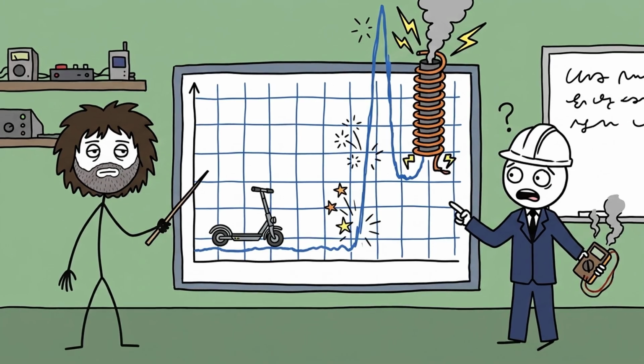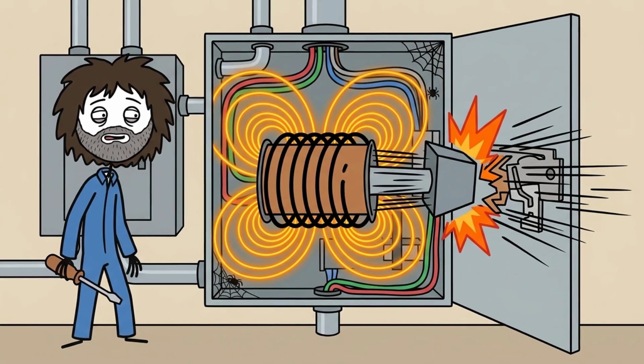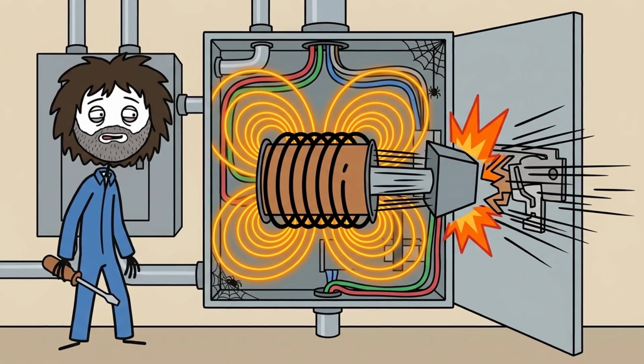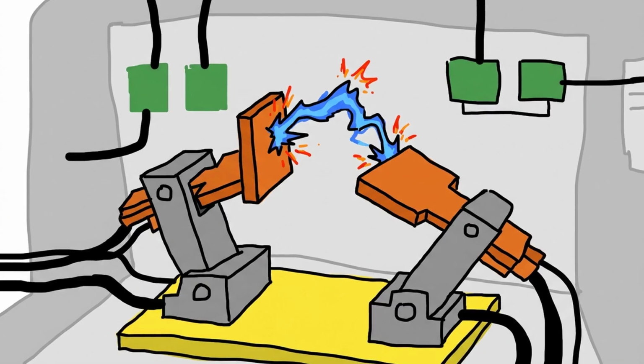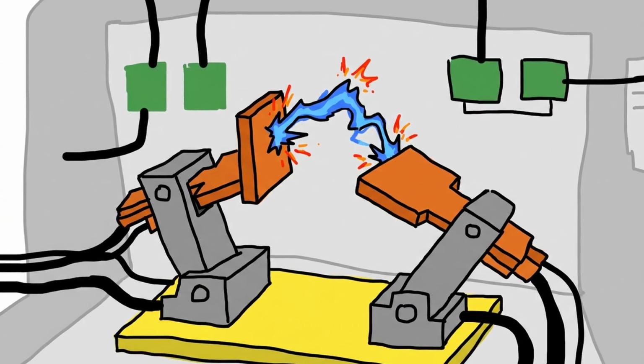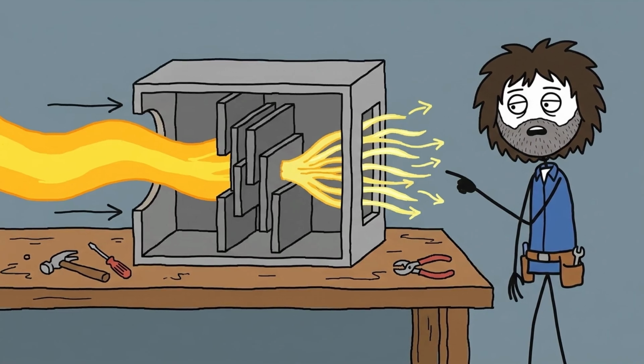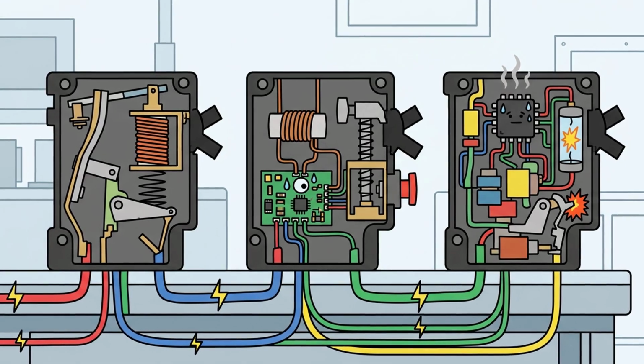When a high current breaker trips under load, physical separation of copper contacts creates a high voltage plasma arc across the air gap. To prevent this arc from destroying breaker housing or welding contacts shut, every breaker features an arc chute. The arc chute is a stack of isolated steel plates.